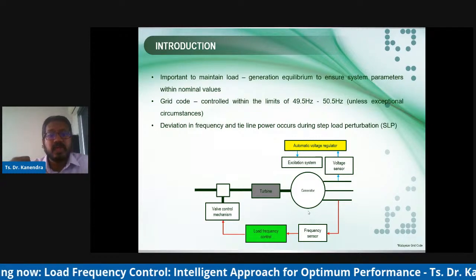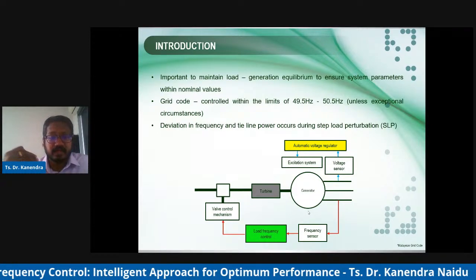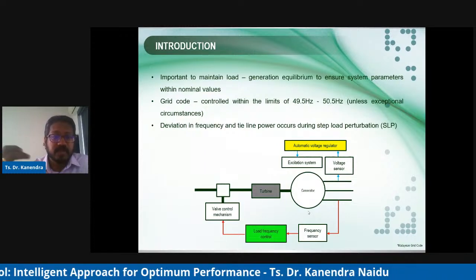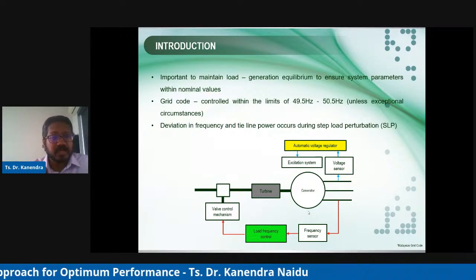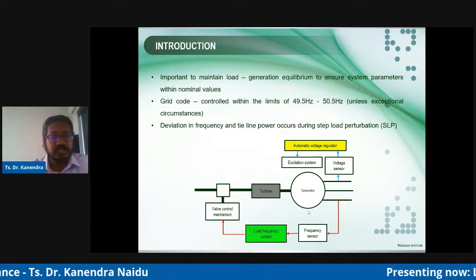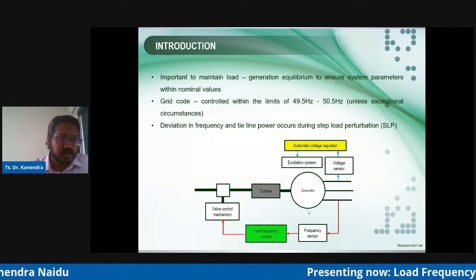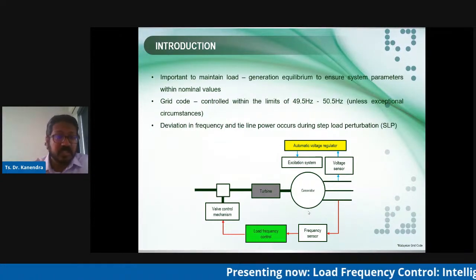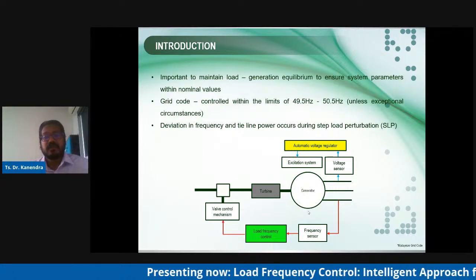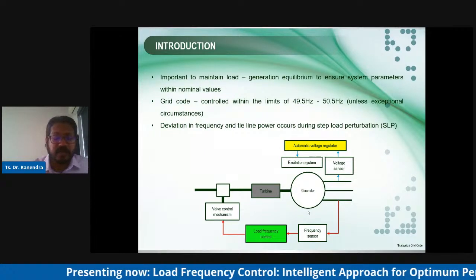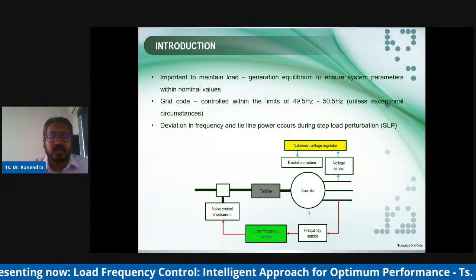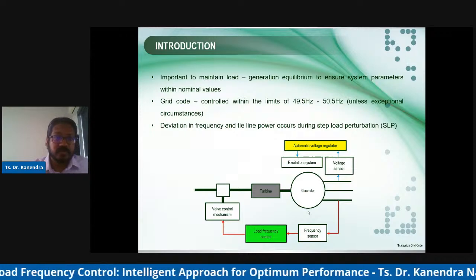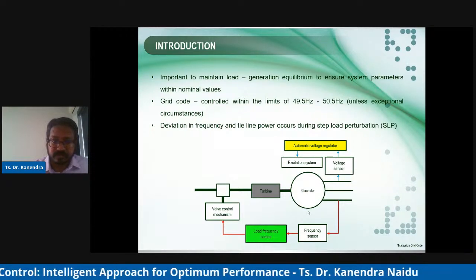And similarly, you have a voltage sensor and you have an AVR. We call it an AVR, an automatic voltage regulator, and you have an excitation system. This excitation system is for the DC excitation, and then you are able to increase or decrease the voltage, right? So when we talk about frequency, we are talking about the active power control, and when we are talking about voltage, we are talking about the reactive power control. So they are interlinked.